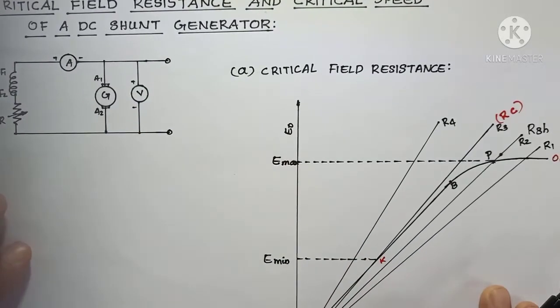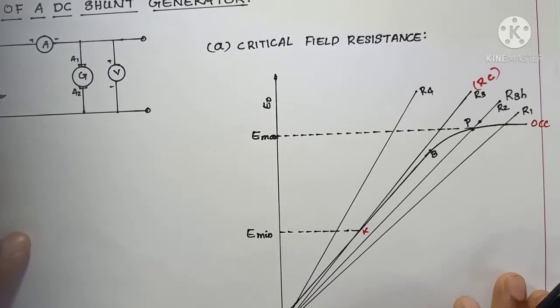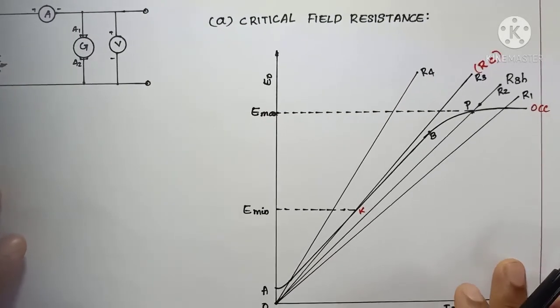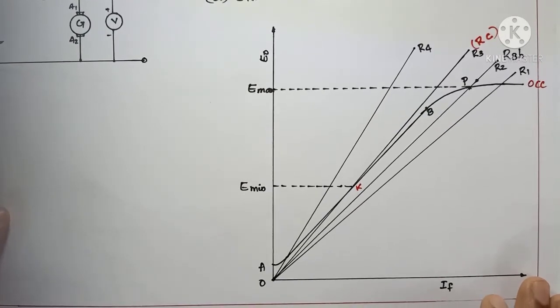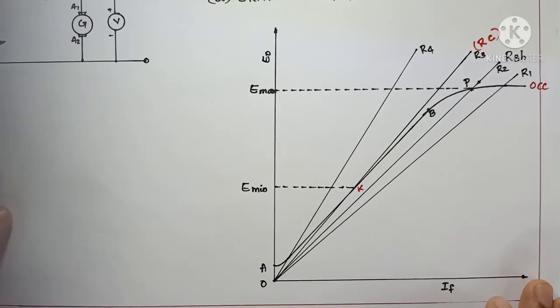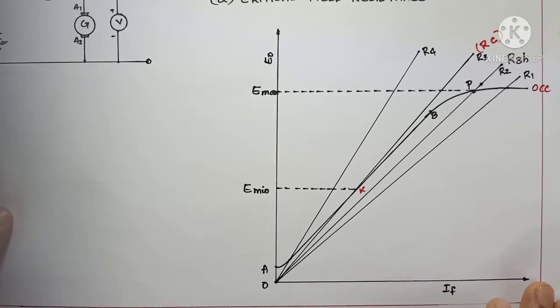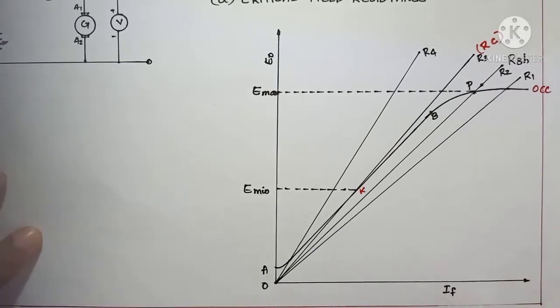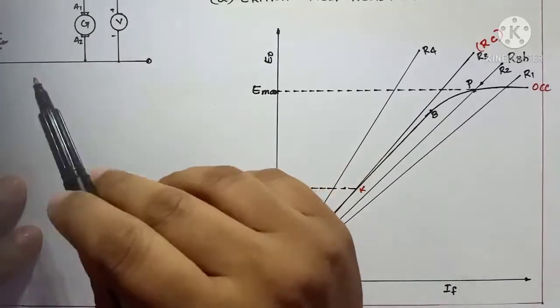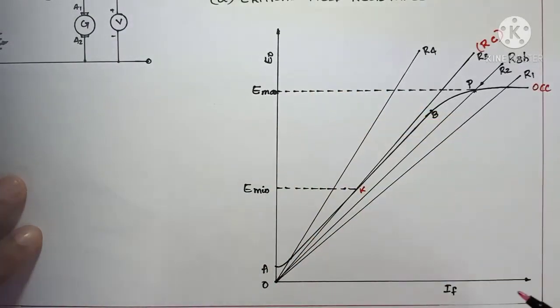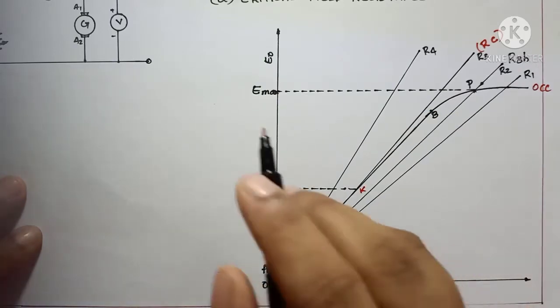The corresponding voltage for each value of IF field current can be measured as the terminal voltage using this voltmeter. You will get the open circuit characteristics from the relationship between E0 and IF. E0 is nothing but the no-load generated EMF or no-load induced EMF, and IF is the field current. If you increase your field current using the rheostat in each step, you will get a particular value of IF and the corresponding voltage.